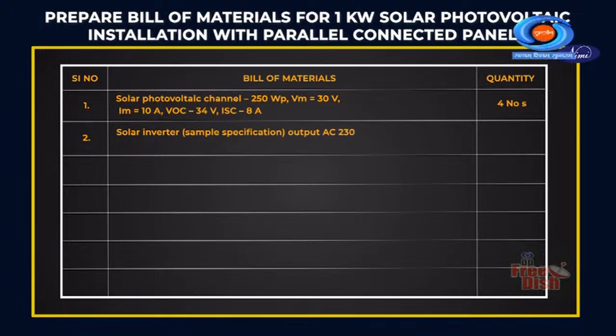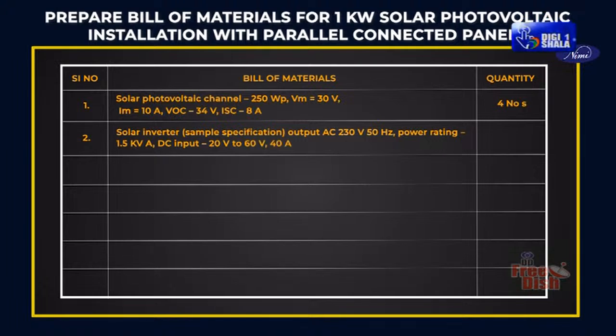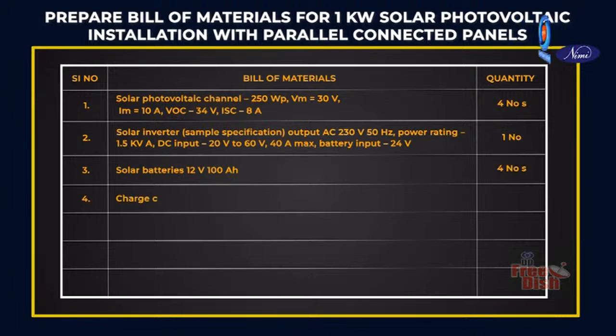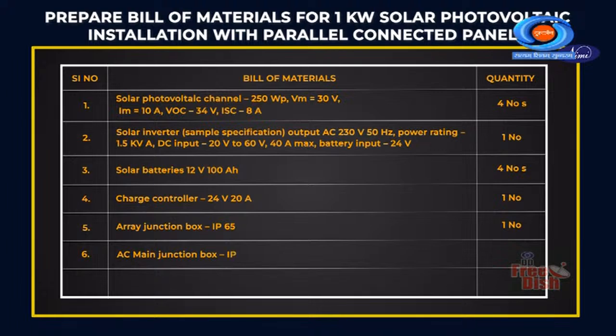Solar inverter sample specification. Output AC 230 volts 50 Hz. Power rating 1.5 kilovolt ampere. DC input 20 volts to 60 volts, 40 amperes maximum. Battery input 24 volts, 1 number. Solar batteries 12 volts 100 ampere hour, 4 numbers. Charge controller 24 volts 20 amperes, 1 number. Array junction box IP65, 1 number. AC main junction box IP65, 1 number. Suitable connecting wires with disconnectors as required.